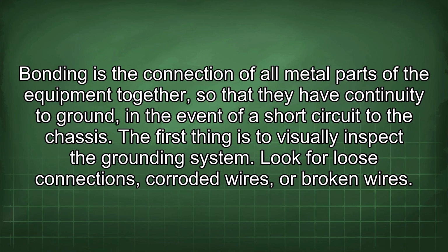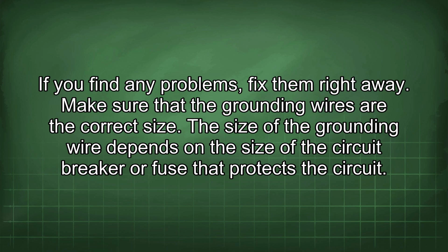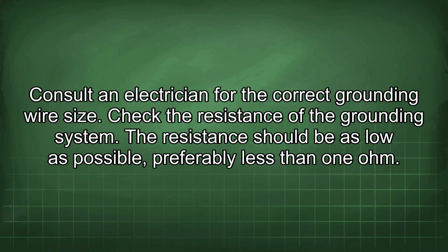The first thing is to visually inspect the grounding system. Look for loose connections, corroded wires, or broken wires. If you find any problems, fix them right away. Make sure that the grounding wires are the correct size. The size of the grounding wire depends on the size of the circuit breaker or fuse that protects the circuit. Consult an electrician for the correct grounding wire size.